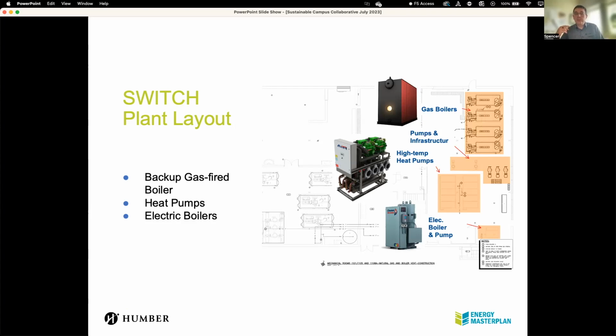We're going to bring that heat from the people back to the central plant, and it's going to arrive at 25 to 30 degrees C or so. Instead of pushing that through the cooling tower like we do now and throwing the heat away, we're going to put it through a single-stage heat pump, move that temperature from 25 degrees to 70 degrees, and put it back in the heating loop. So essentially we've recovered the heat from the people at the central plant. The engineers tell us this is probably going to be 40% of our heating load. That's a lot. Yes, we have to use some electricity to pump things around and run the heat pumps, but for 40% free heat, that's pretty impressive.